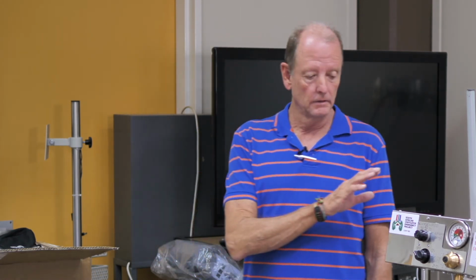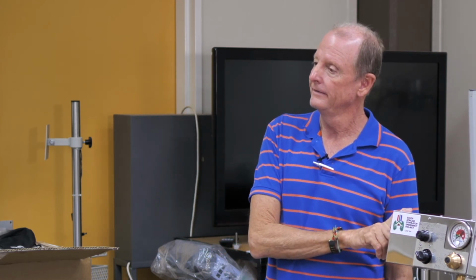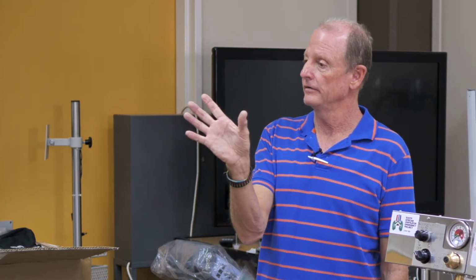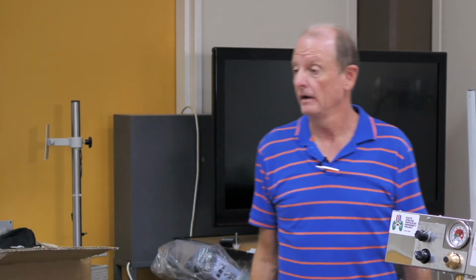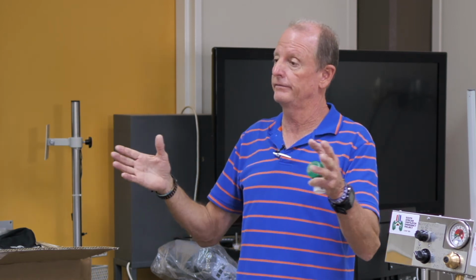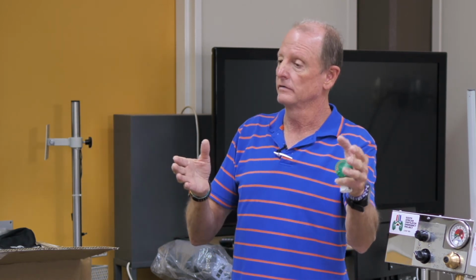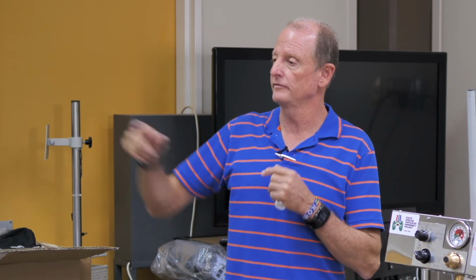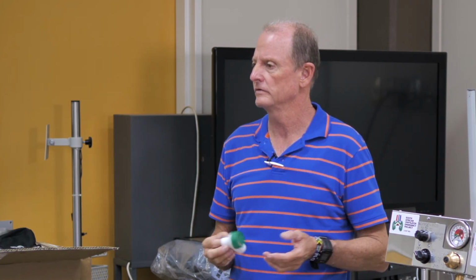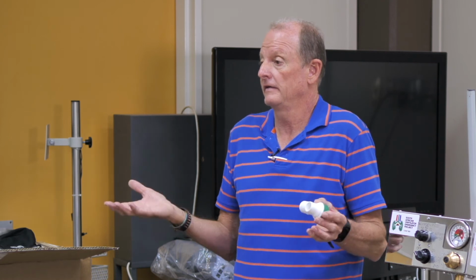But there again, if that was 1 per 1, if you have a bank of those driving 5 of these, that's the other side. Have you got sufficient flow on a bank of 5 cylinders, driving 6 of those? Will there be sufficient flow? If they're all on 60 liters a minute, think of that. You're probably not going to have it, no. No, not through you. It's basically quarter, isn't it? Quarter inch, yeah, oxygen pipes. And that's a standard. You don't get any bigger.